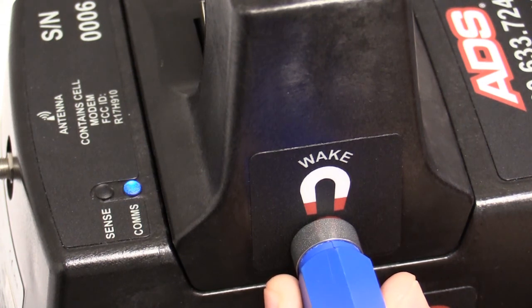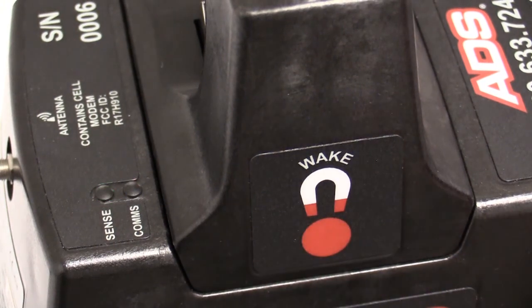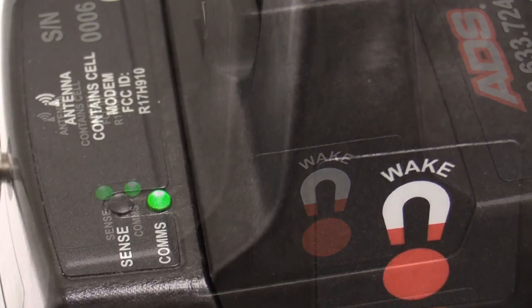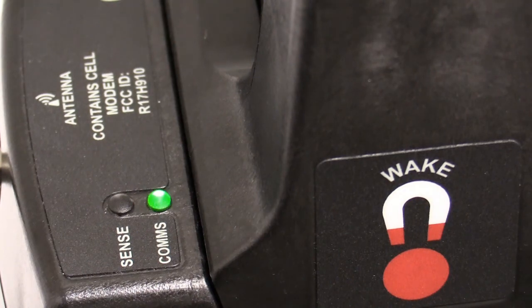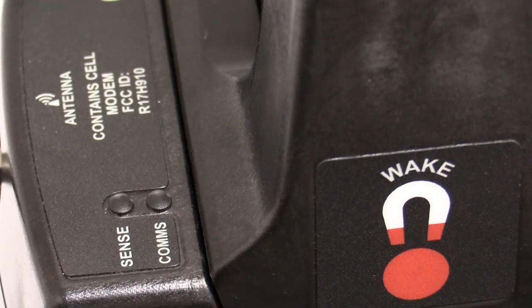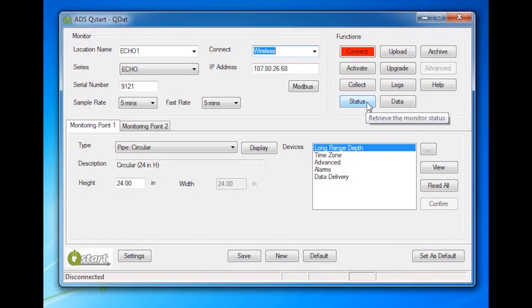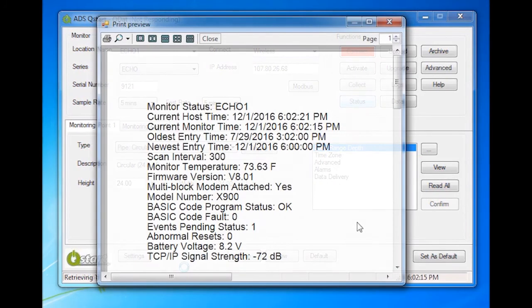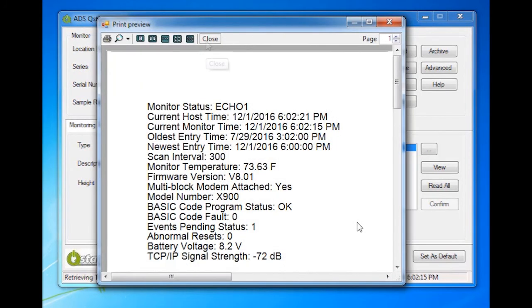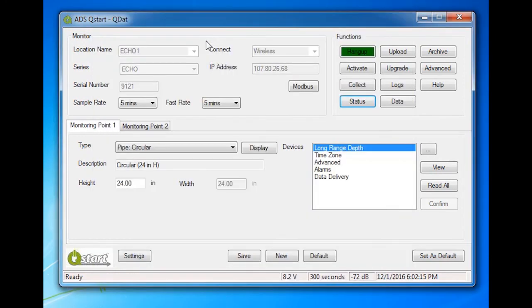Hold the magnet for another 1-2 seconds and then quickly remove the magnet. The comms LED will change to a slow flashing green when the modem connects to the network. Click on the Status button in QStart. Once connected and the monitor status has been retrieved, the status screen will display. Close the monitor status screen. Wireless communication has been verified.